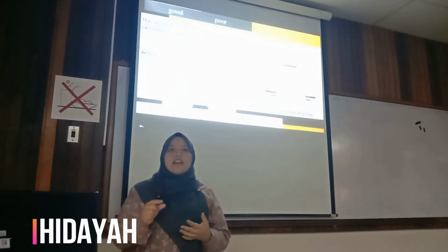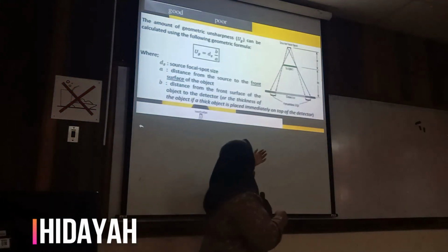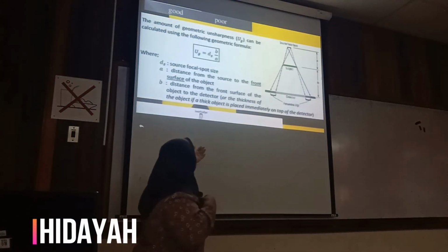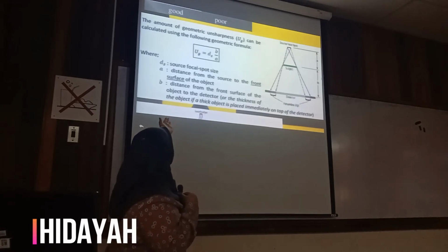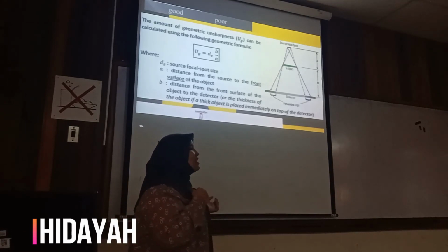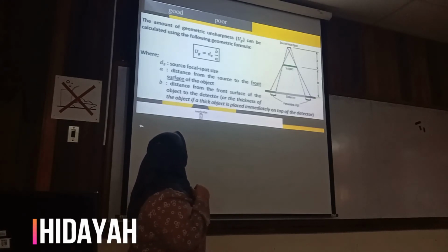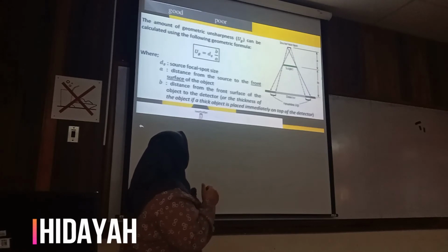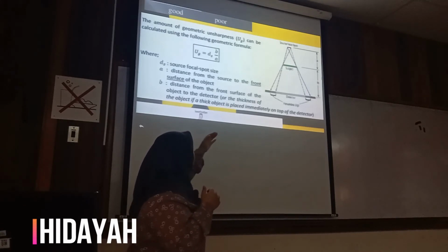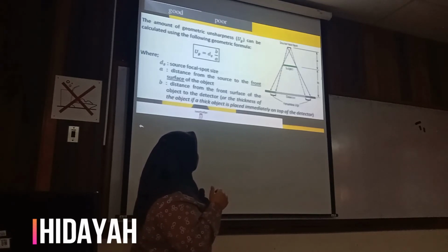and this 1/100 of the thickness can be up to 1 micrometer, and this one we call the length of penumbra. So as we can see here, this one is the penumbra, and it can be calculated by using the formula of unsharpness. Unsharpness is equal to the focus spot size multiplied by the ratio of B/A, where B is the distance between the subject surface and the film or detector, and A is the distance between the source and the subject surface.